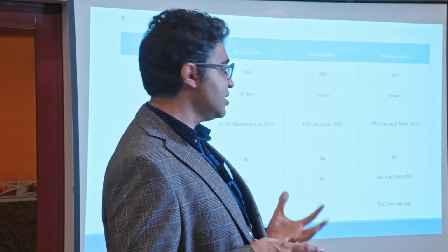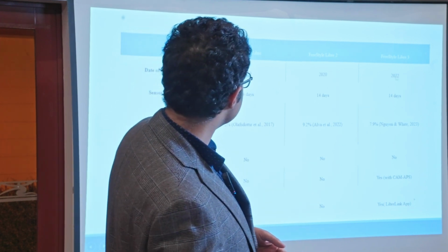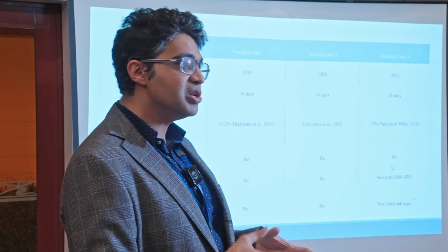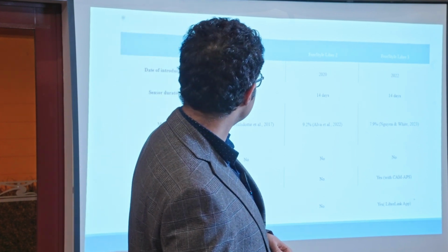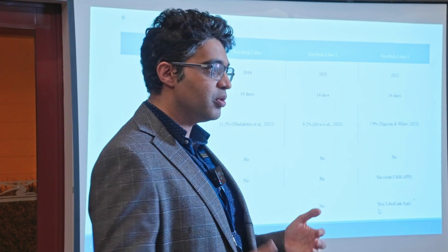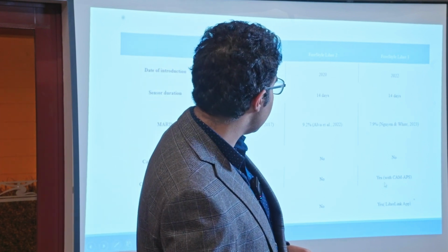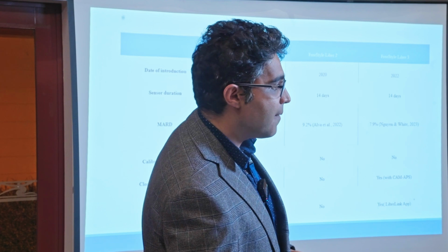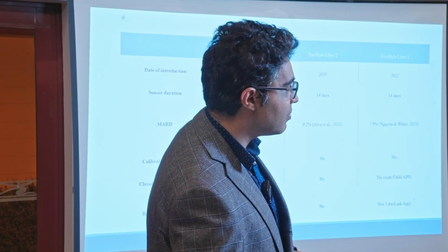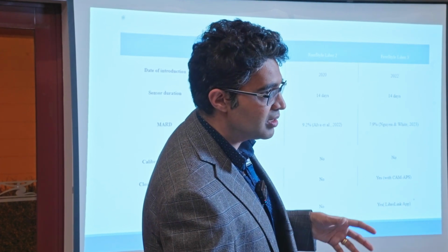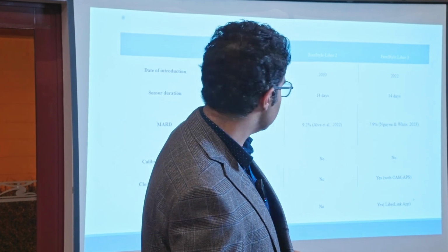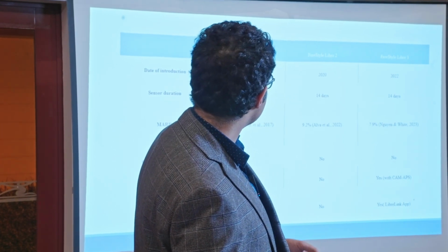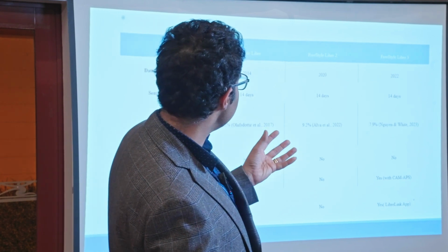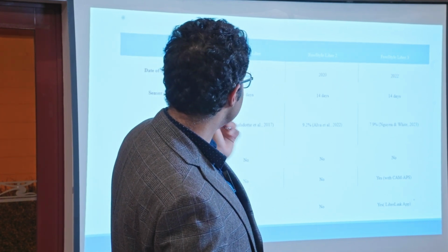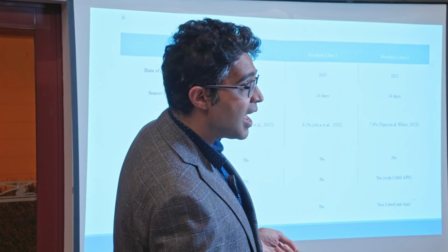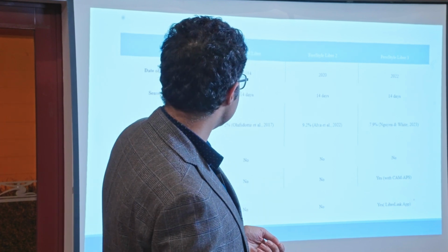With how these devices have evolved, there's now a third generation device which is very much a continuous glucose monitor and integrates with insulin pumps to provide what's known as closed loop integration, which is effectively the pump and the continuous glucose monitor talking to each other, much in the way that a functional human pancreas would. The accuracy has increased over time. The sensor duration hasn't changed, and none of these devices require calibration.